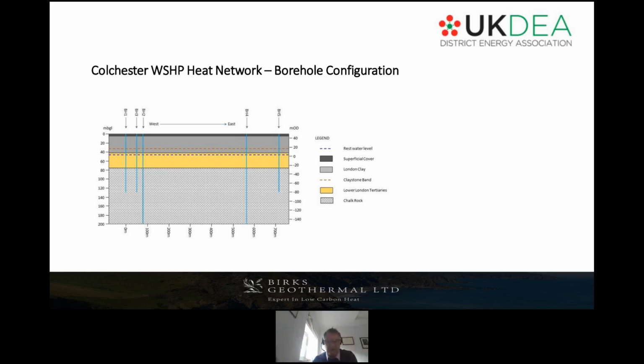And here is the borehole configuration at the Colchester Northern Gateway, where we had 2 abstraction boreholes drilled to depths of 130 to 200 meters and drawing water from the chalk aquifer, pumping that water over a distance of over half a kilometre to re-injection boreholes where the water is put back into the ground. And generally, that's a licensing requirement in the UK to preserve groundwater for other uses than just heating and cooling.